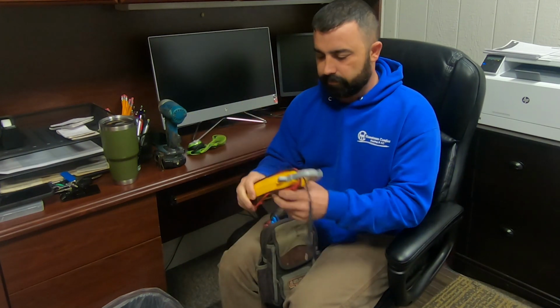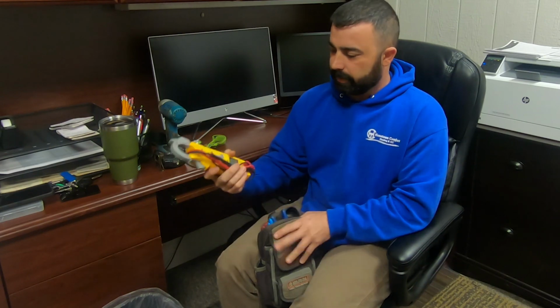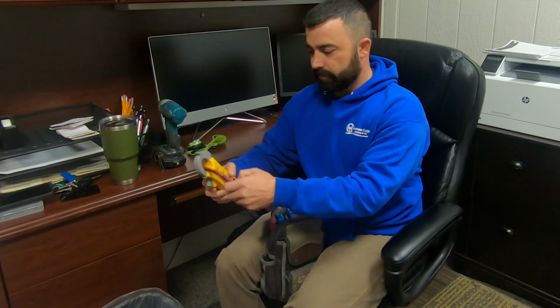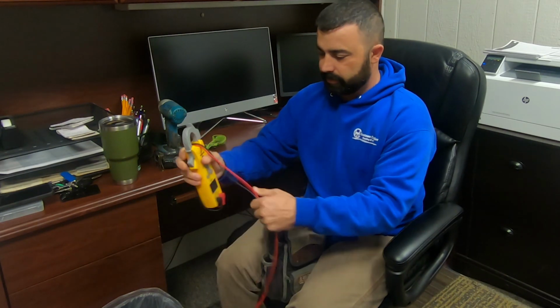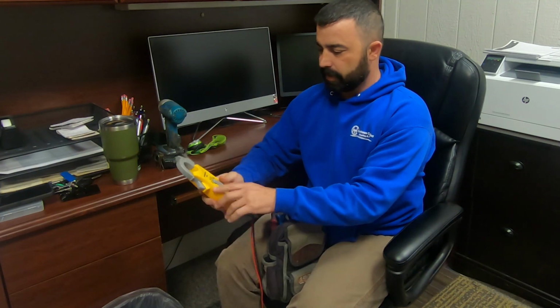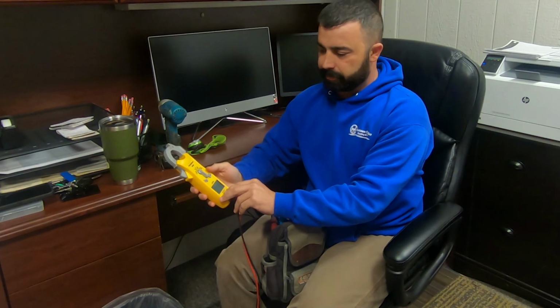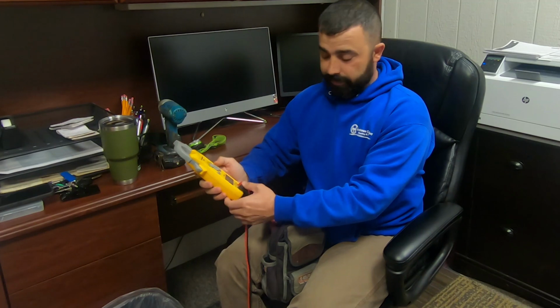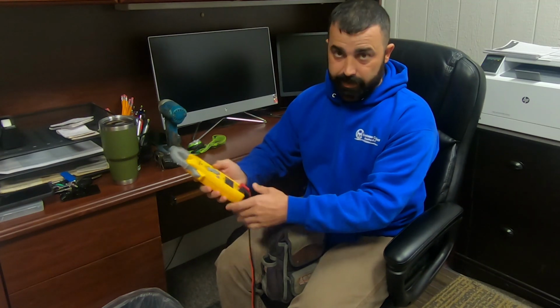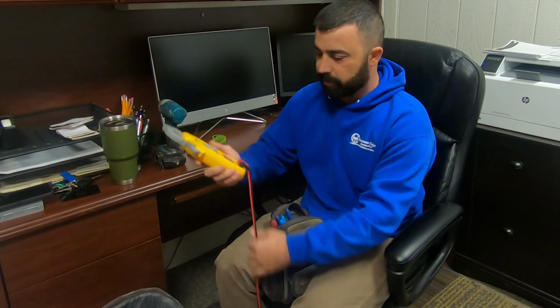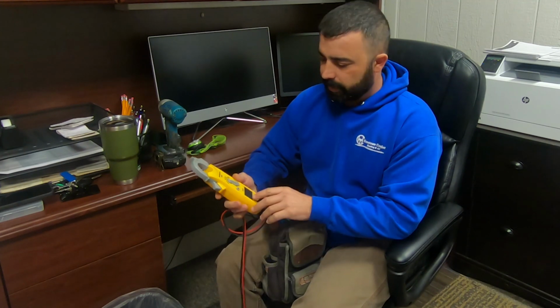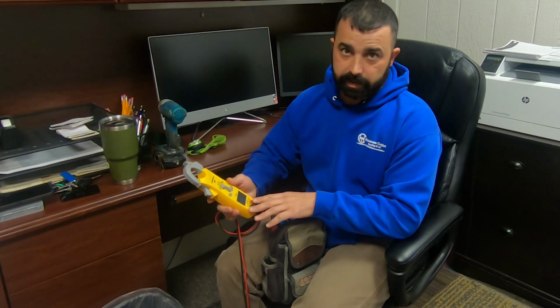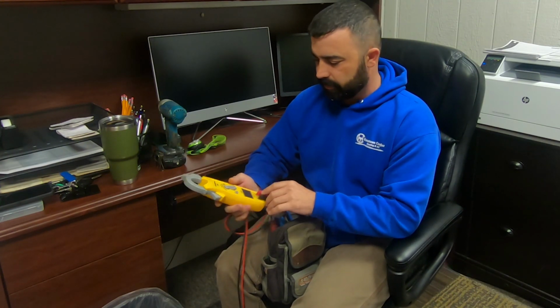Need a good multimeter. I like one that has multiple functions. This one, for instance, I can do temperature if I plug in a temperature probe. I've got the temperature probe in my truck. I usually don't keep that in my bag here unless it's summertime. Of course, we're in winter right now, but that way I can check superheat and subcool on systems.